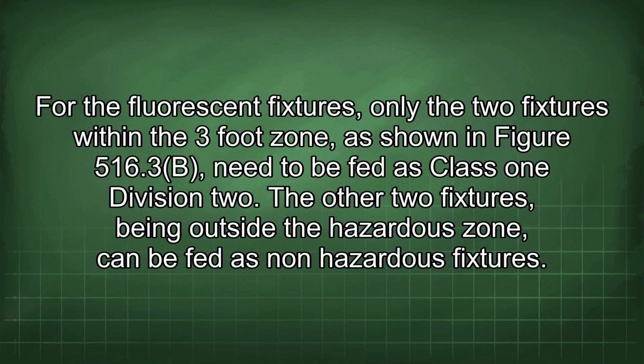For the fluorescent fixtures, only the two fixtures within the 3-foot zone, as shown in Figure 516.3(b), need to be fed as Class 1 Division 2. The other two fixtures, being outside the hazardous zone, can be fed as non-hazardous fixtures.